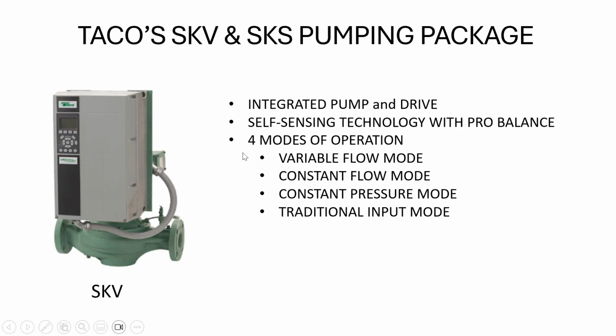No problem, Rich. Here's the 4 modes of operation. Variable flow mode, and that's probably 80 to 90, if not more, percent of the projects that we've sold for our SKVs, SKSs, and others, and I'll talk about that as well. But you can also very, very easily put it in constant flow mode. So maybe for a primary, secondary system on the primary system. Constant pressure mode, I'm not sure we do too many of those. I'm not even sure how it would work on a booster system, but possibly for a booster system. And just as important, and think outside the box. I always challenge people to think outside the box. Traditional input mode, meaning you can disable these first 3 modes and accept a traditional signal into that drive.